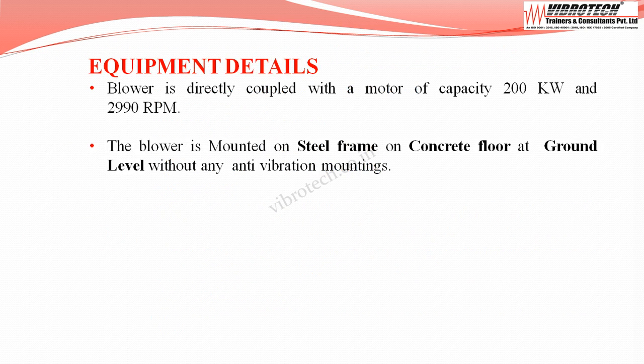The blower under study is directly coupled with a motor of capacity 200kW, running at 2990 RPM. The blower is mounted on a steel frame on a concrete floor at ground level, without any anti-vibration mountings.